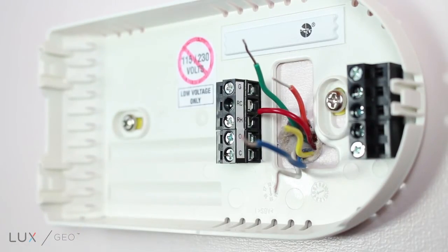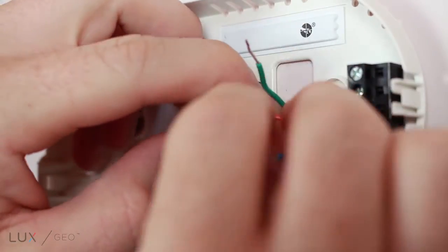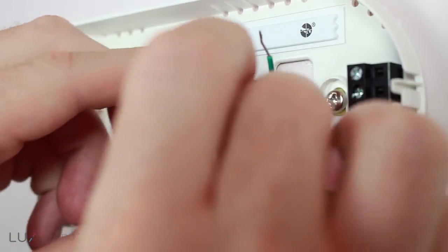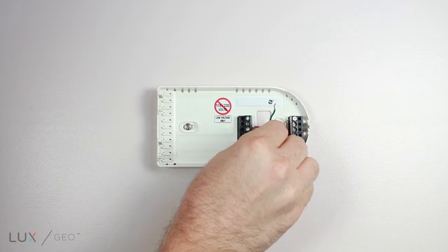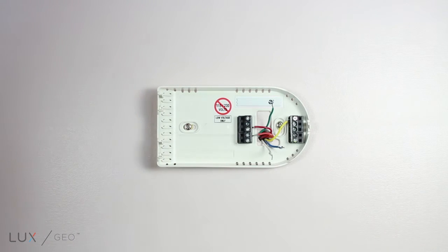The 24 volt power wire is red and will be connected to the RH terminal. The reversing valve is orange and will be connected to the O terminal. The heat pump outdoor unit is yellow and will be connected to the Y1 terminal.